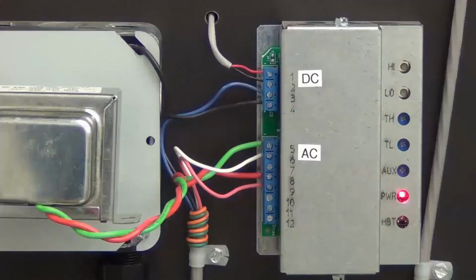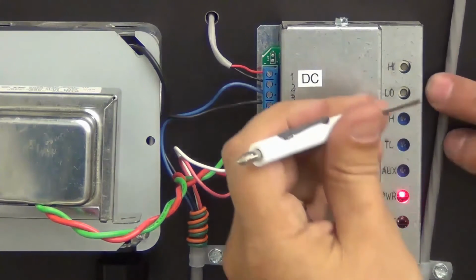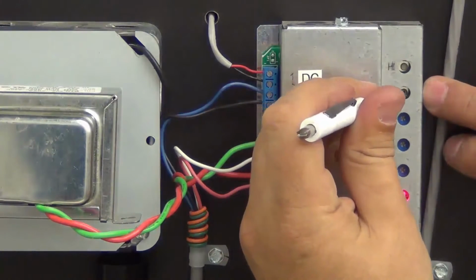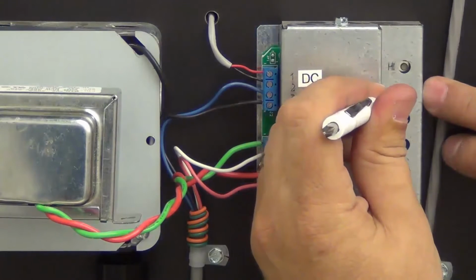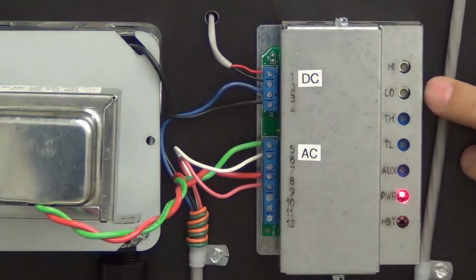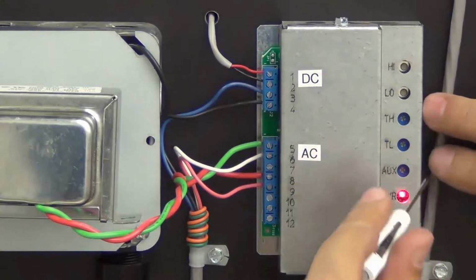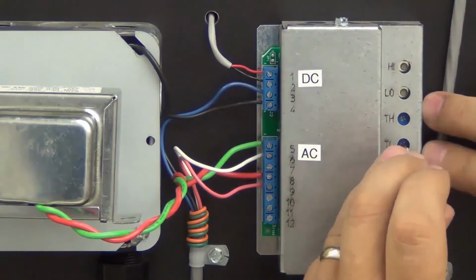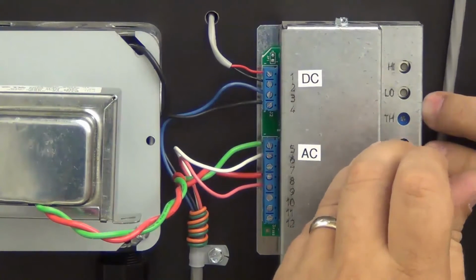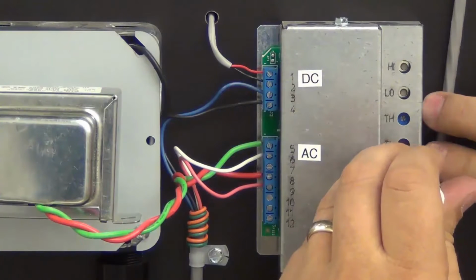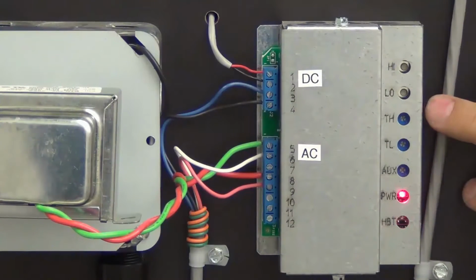Turn the exhaust fan to low. On the controller, push the low button for a couple of seconds. Adjust the trim pot to match the exhaust airflow. The control will now proportionally adjust the fan airflow between high and low. Please note it may take a few seconds for the makeup air fan to adjust to the exhaust fan.